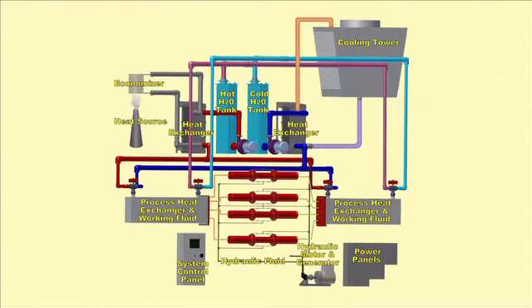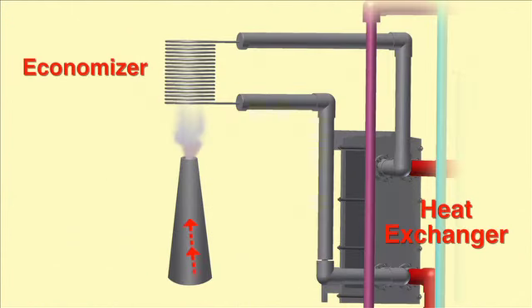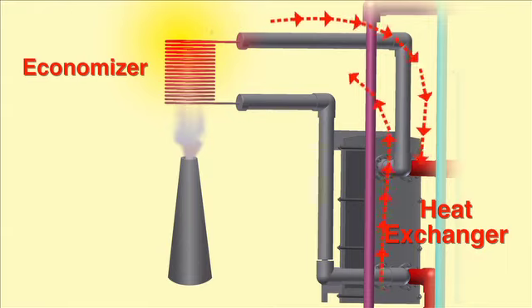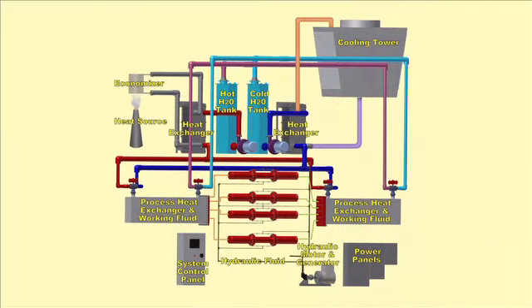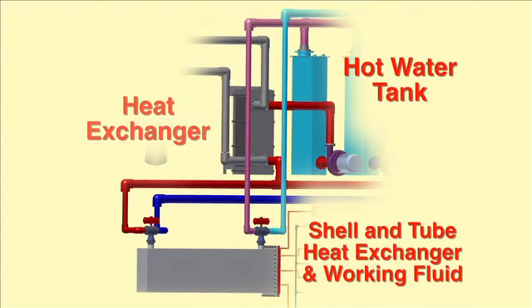A heat source is captured in 2 ways. First, if the heat source is an airstream or steam, the heat is captured by circulating water through an economizer or heat exchanger. This captures the heat and transfers it into a fluid, such as water or a thermal oil. The heat from the fluid is then circulated through a second heat exchanger, which heats the closed-loop water system on the Thermalicity engine. This closed-loop hot water at 180 degrees Fahrenheit is circulated around specifically designed shell and tube heat exchangers, which contain a working fluid.